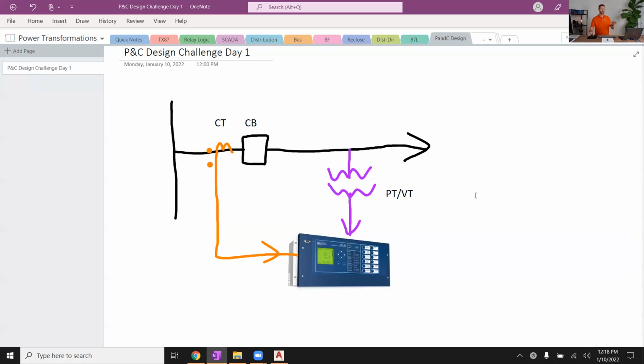You know, sometimes I've drawn this as a line side PT. I'm talking about this is the line side over here. This is the bus side. And so over here, we've got sometimes these PTs, these voltage signals come from bus PTs instead of line PTs. But this is probably the more preferred approach if you have them line PTs available. Note that another term you might use is that these are bus side bushing CTs on this circuit breaker, because they're on the side of the bus closest to the bus rather than the line. But we're using it for line protection. We'll draw that out later to help you understand.